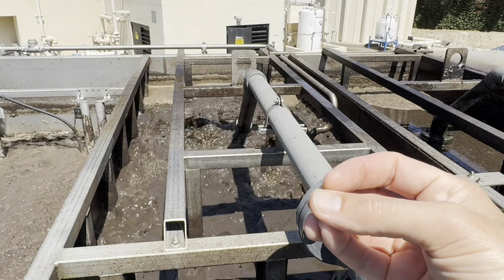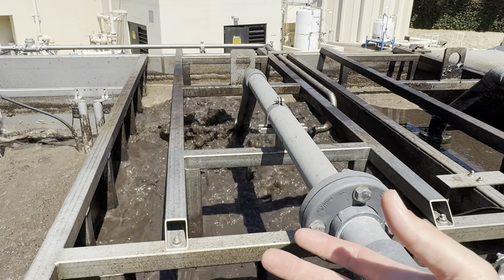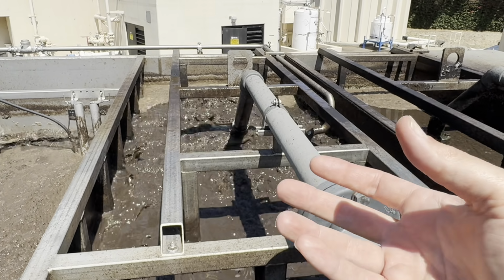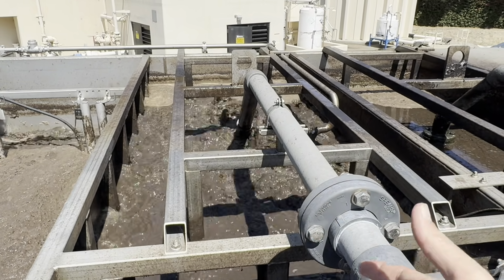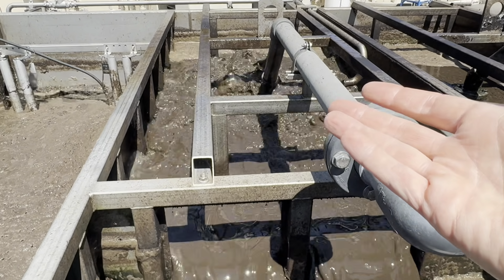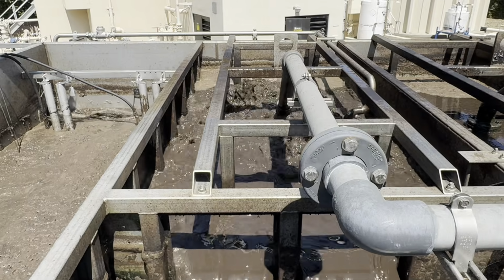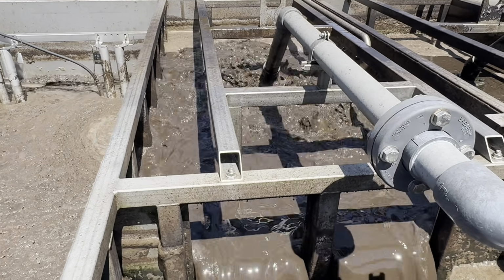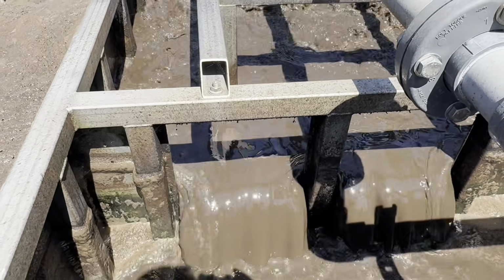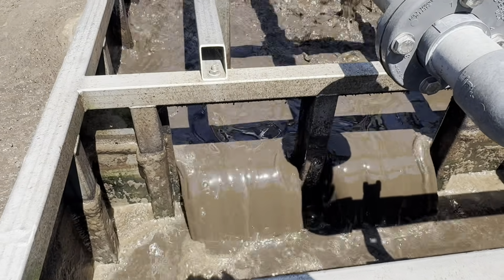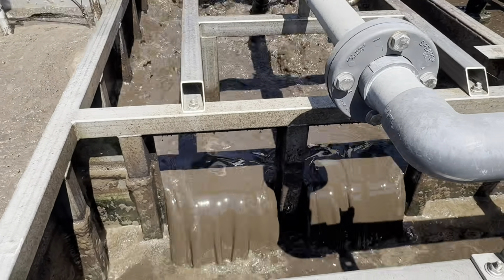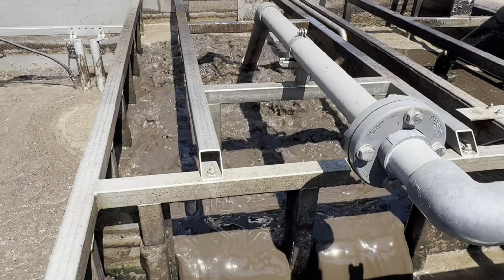And the floc in a normal clarifier would settle down, and we're going to talk about that on the whiteboard a little later. But in here I need good floc, because without good floc, my membranes would blind. And so what happens is we pull that really clean water off of the floc as it passes by, and the air scour keeps the floc moving along. And there's that beautiful RAS. Okay, so let's now go down below, and I'll show you my RAS line and my waste activated sludge pump.